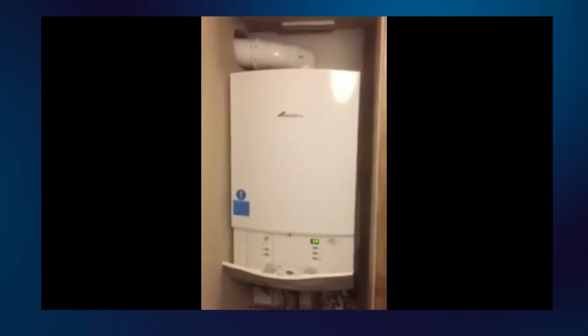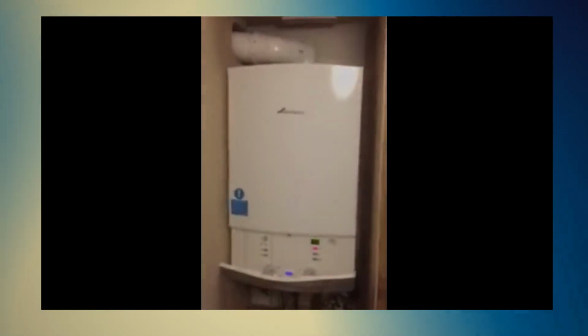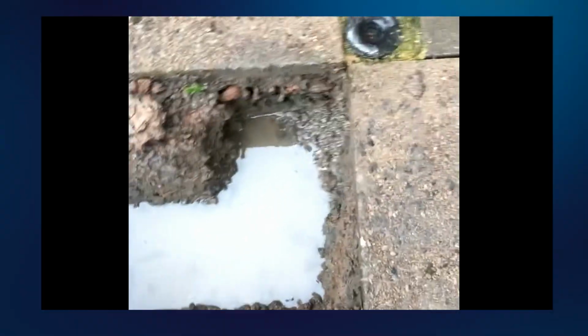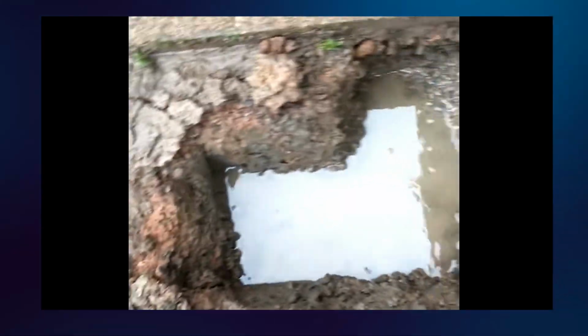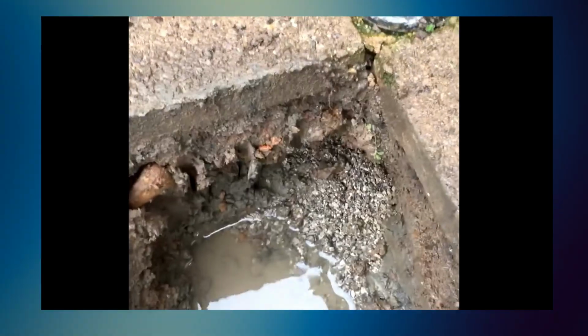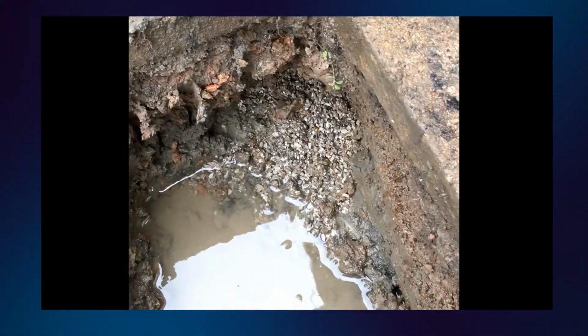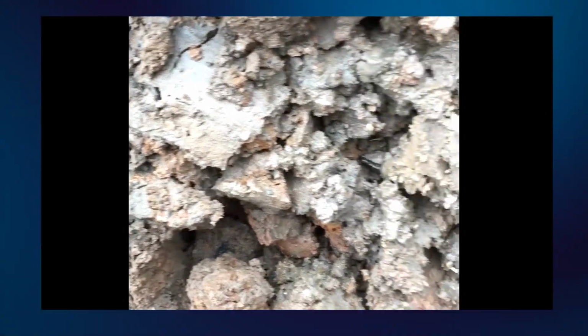Now let's talk about what you can safely do. You can check whether other gas appliances work. You can check whether the boiler has power. You can check whether the gas isolation valve appears open. You can check the system pressure on the display or gauge, because some boilers may behave differently when pressure is very low. You can visually check the outside flue terminal for obvious blockage. You can check for a frozen condensate pipe in cold weather. You can reset the boiler once, according to the manual. You can check whether the fault happens only during heating, only during hot water, or both. That information is very useful for the technician.